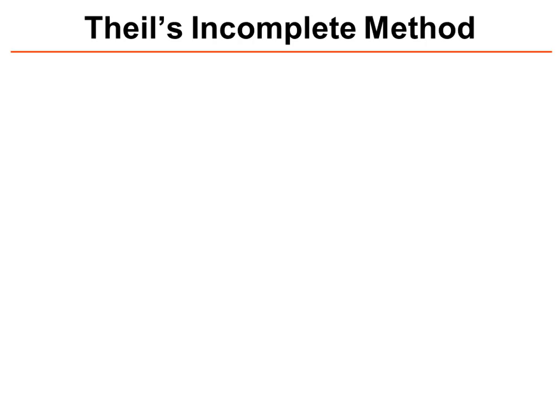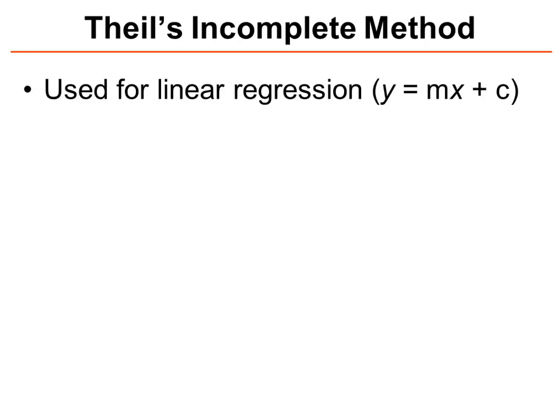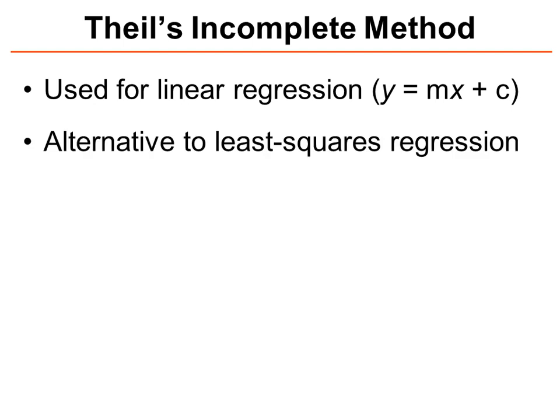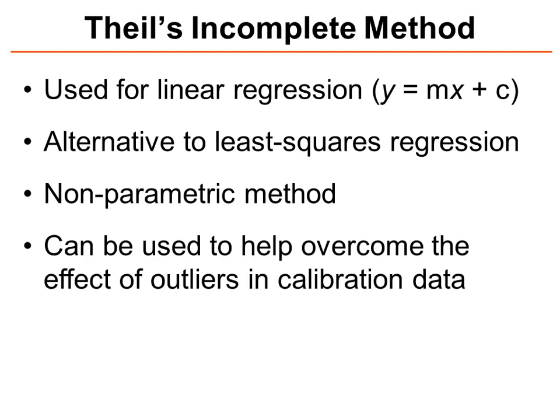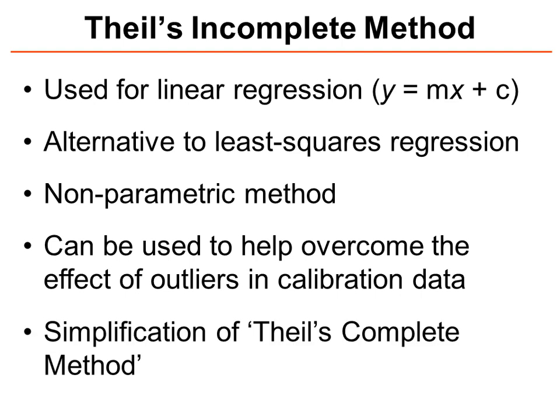In this lecture I'm going to explain Thiel's incomplete method. This method is used for linear regression to fit an equation of the form y equals mx plus c to a set of data. It's an alternative to least squares regression, but an important difference is that this is a non-parametric method, so it doesn't assume that the errors between the data points and the line of best fit are normally distributed. It can be used to help overcome the effect of outliers in calibration data, and it's a simplification of Thiel's complete method.